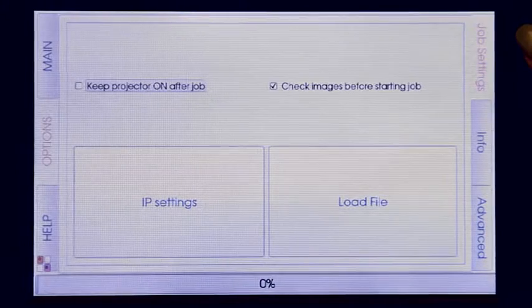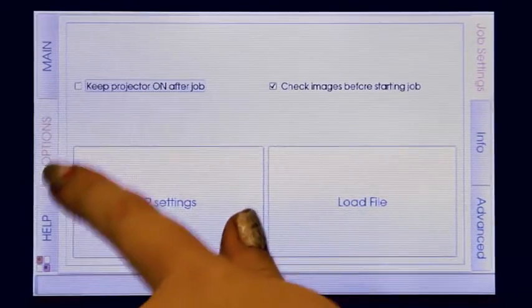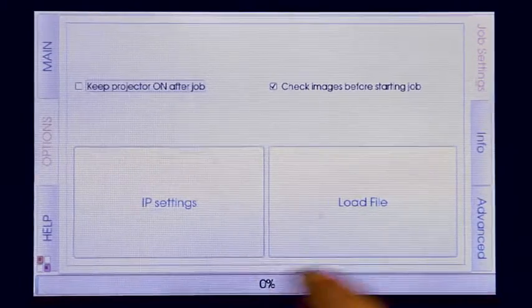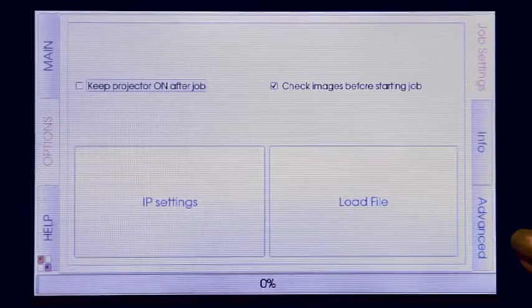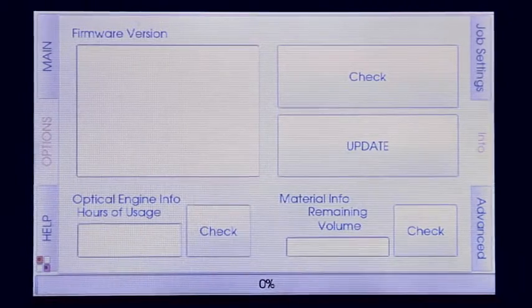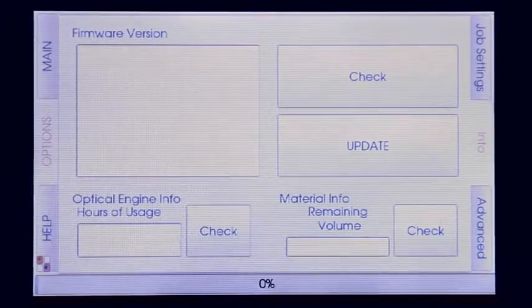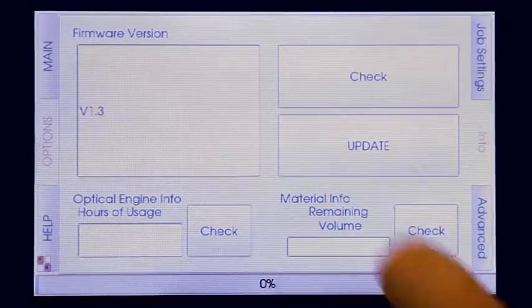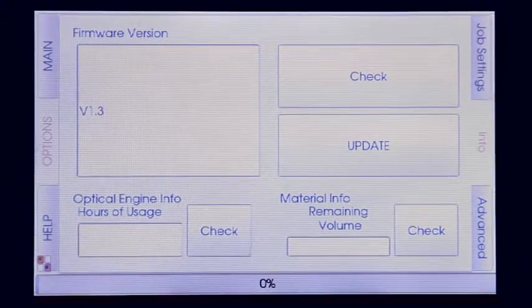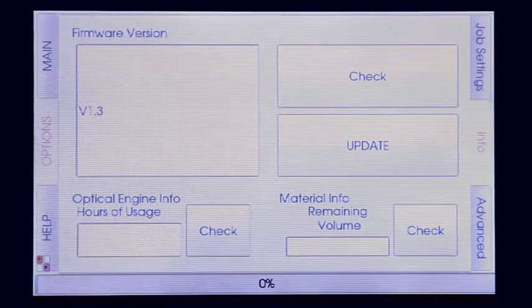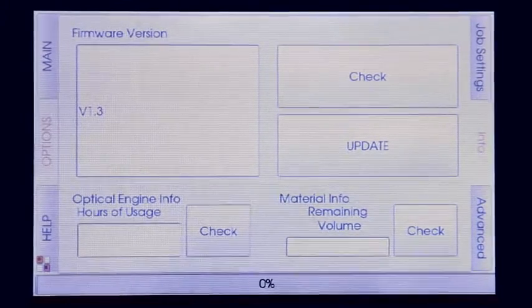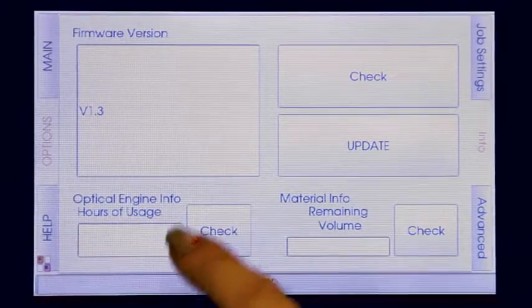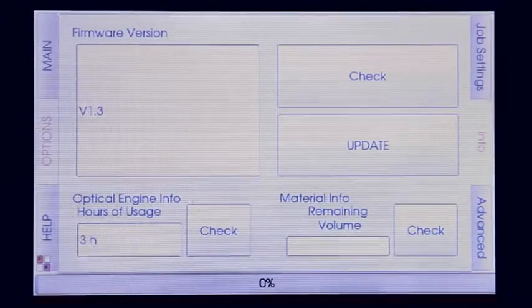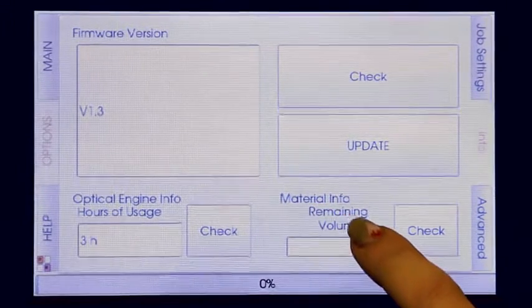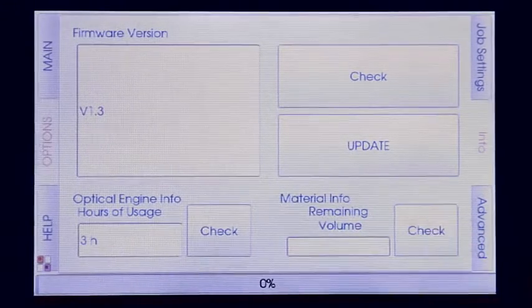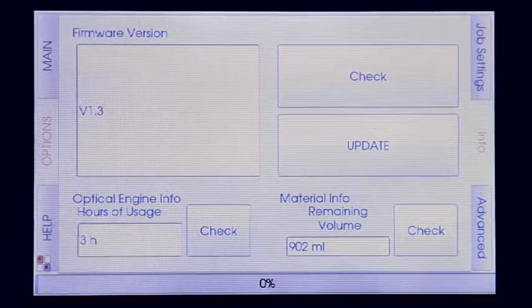On the right, you'll notice we also have 3 tabs inside of the Options tab. We have Job Settings, which is the tab I just described, Info, and Advanced. If I click on the Info tab, this gives me all of the information about the machine. At the top, if I click Check, it will give me the version of the firmware I am using. This is important sometimes to tell technical support so we know what version of the firmware you're using. Below that, you can check how many hours the light has been on by pressing check. This one's been on for 3 hours. And then we can check the remaining volume left on our material tag by clicking check. It reads the tag and tells us how many milliliters we have left.